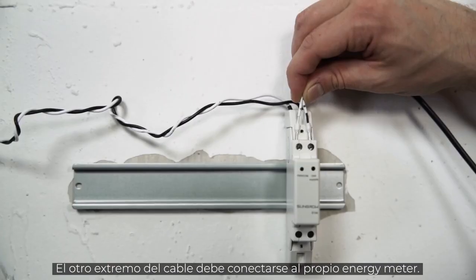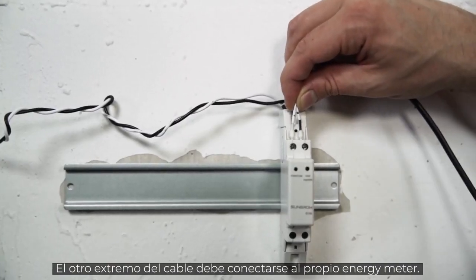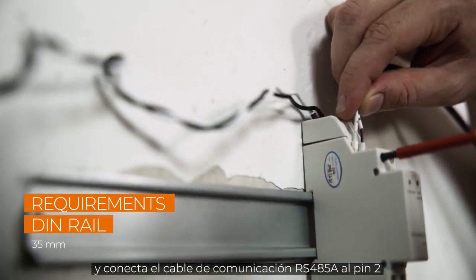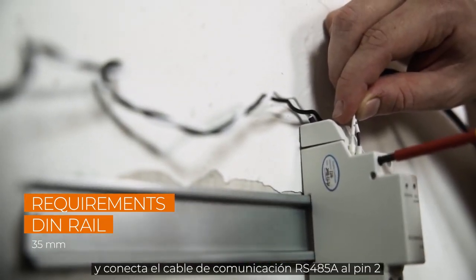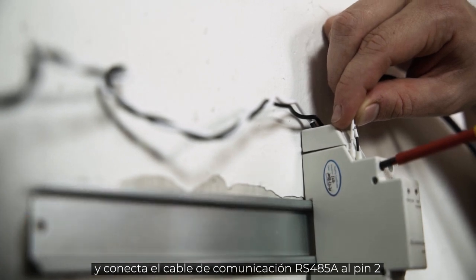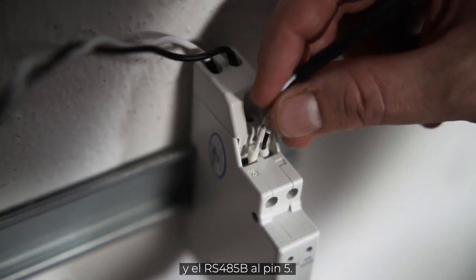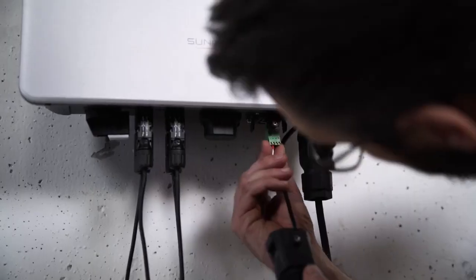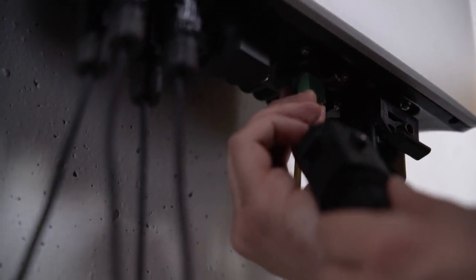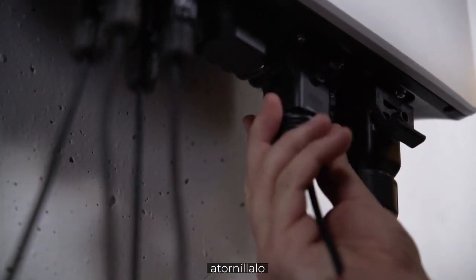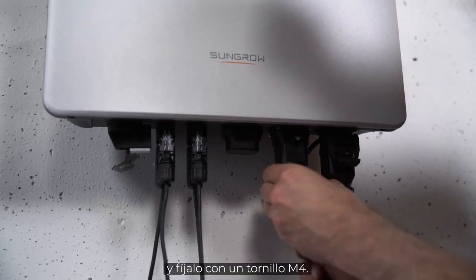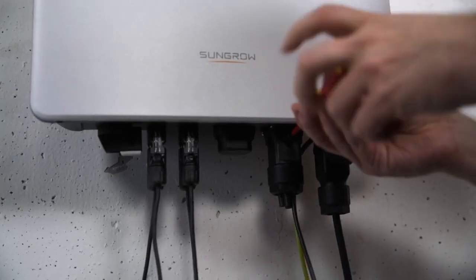The other end of the cable needs to be connected to the smart meter itself. Mount the meter to a DIN rail and connect the communication cable RS485A to pin 2 and RS485B to pin 5. Plug it in, screw it, and fix it with an M4 screw.